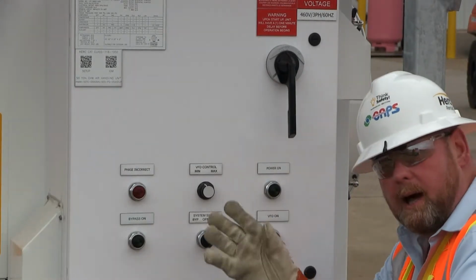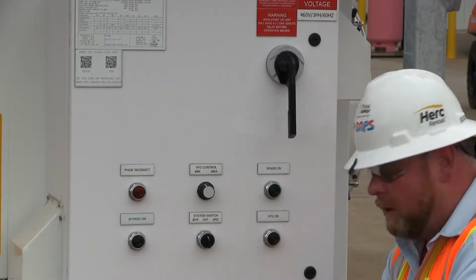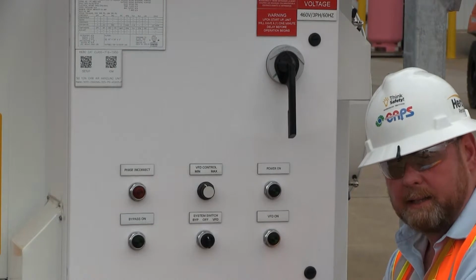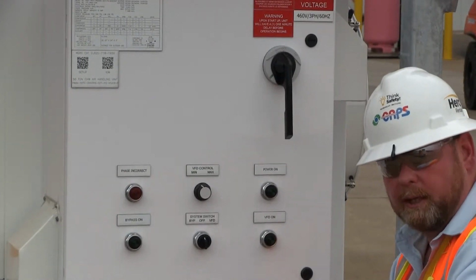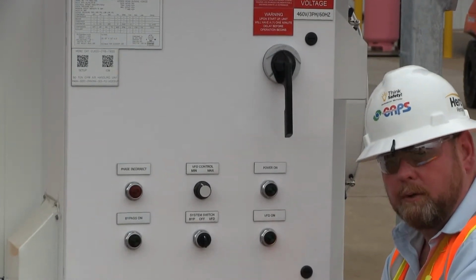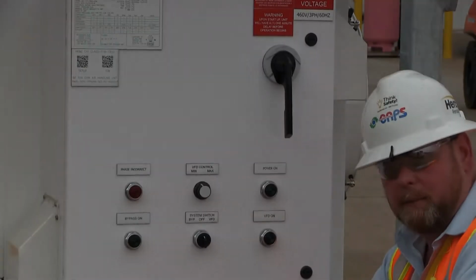We're going to go and lock and tag out our main power source. We're going to have to reverse two of our leads here, the L1 and L2, in order to get the phase correct. Please note that you never change the cam locks with the cable energized.